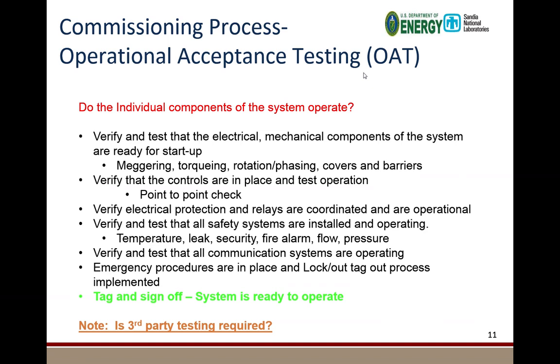Moving on, now we head right to the commissioning process. This is now the construction is complete. Contractor says, I'm done. Now you need to say, okay, does the individual components of the system operate? That's the first step. One by one, test that the electrical and mechanical components are ready for startup. This is when you do your meggering, your torquing, your rotation phasing, making sure all the covers, all the barriers are in place, or all the controls in place, the point-to-point checkout, test the operation.